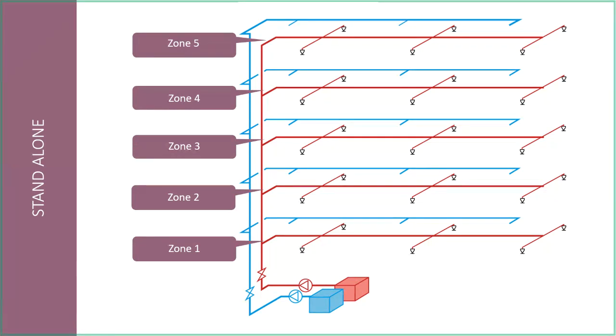In the case of an activation, or if you want to do any kind of maintenance work or alterations on the floor, you can close that valve off, and you have a flow switch which is giving you fire information. Any sprinkler head operating will cause a flow of water down that pipe leading to the floor, and that will set off the alarm on that flow switch, which will then be passed back to some fire alarm panel or BMS system, or various ways in which you configure it. But you've got a signal on that floor to say that there's been an activation and therefore a fire, and that can feed into cause and effects.